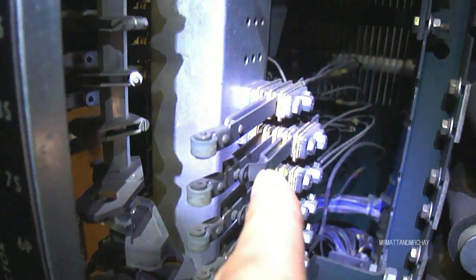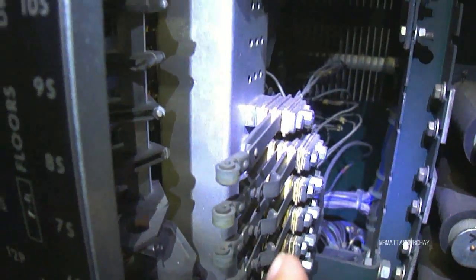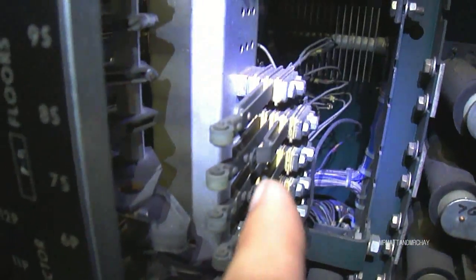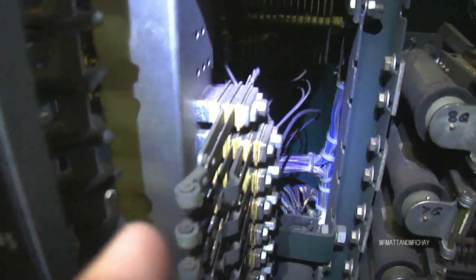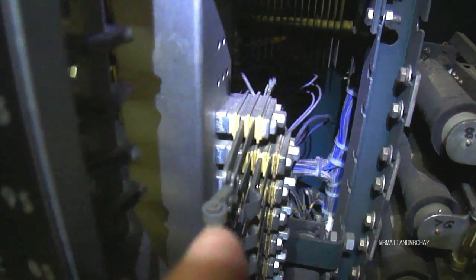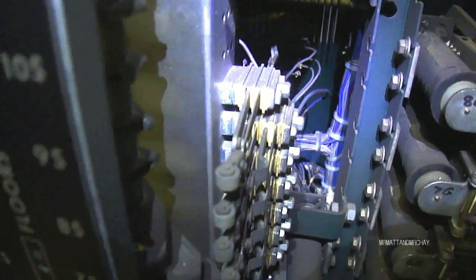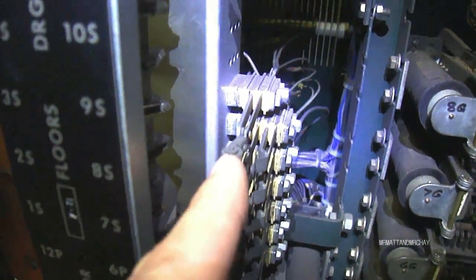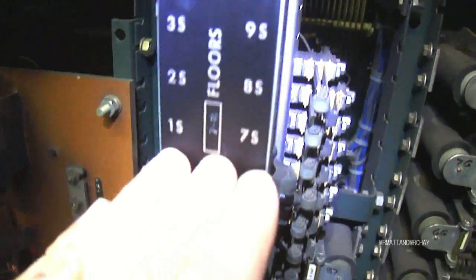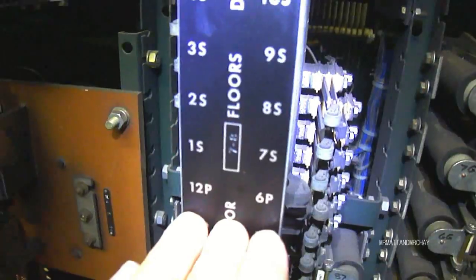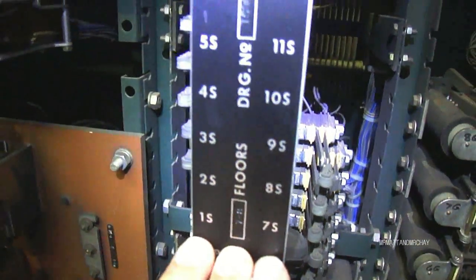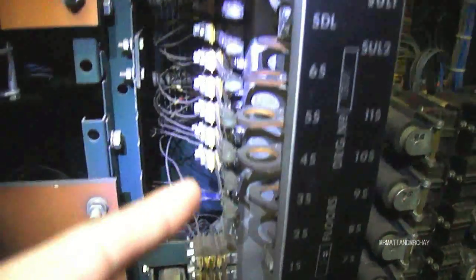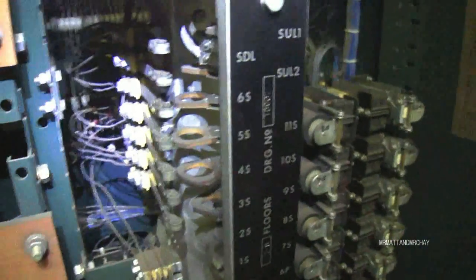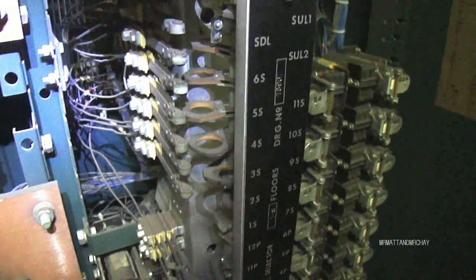See the little contact? Now that is a normally open switch, which means for that switch to activate, it must push the wheel in, which joins them two wires together. This is a different type of switch. This is a normally closed switch. So when that wheel is pressed, it separates the contacts on that side. This switch here is part of the upper set. You see you've got the S contacts and the P contacts. These switches on this side tell the lift which way to go when it receives a call.